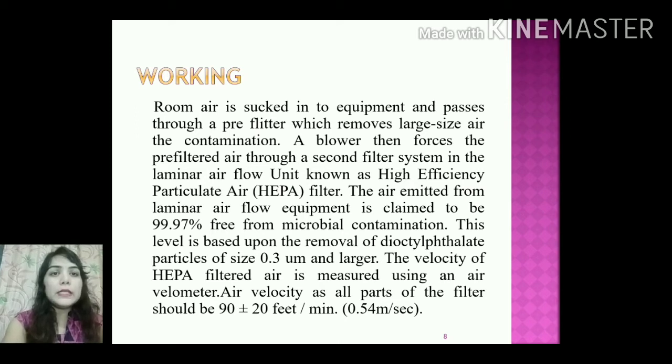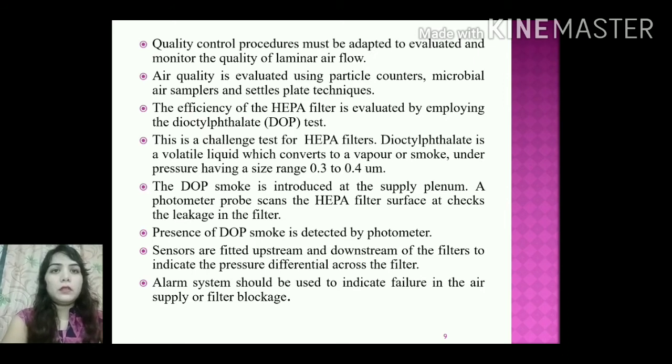To increase the lifespan of the HEPA filter, quality control procedures must be adopted to evaluate and monitor the quality of laminar airflow. Air quality is evaluated using particle counters, microbial air samplers and the settled plate technique.